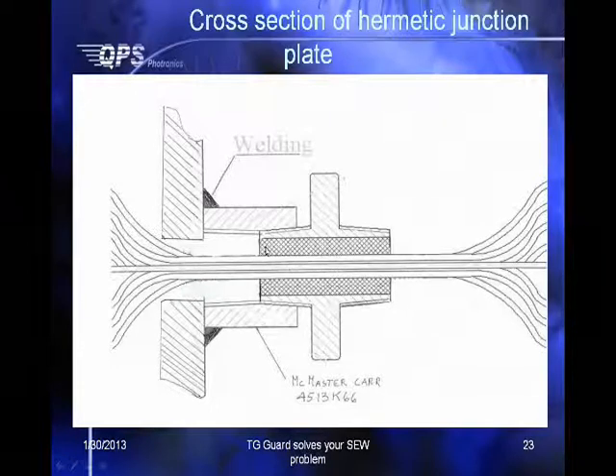By calculation, it will take hydrogen gas 100 years to leak out from the inside of the generator to the outside. Beyond that, having this hermetic junction plate only requires you to open up 2 holes. There are standard parts you can buy and weld onto the body, the wall, or the cover of the generator.